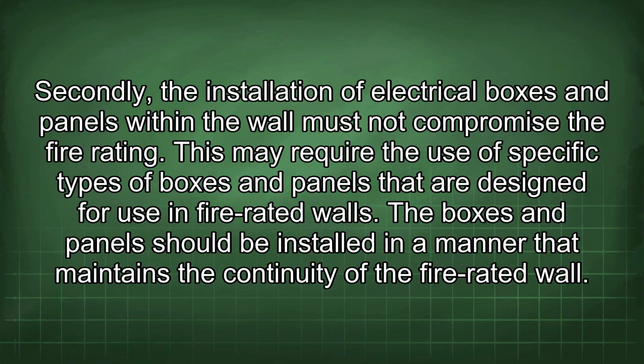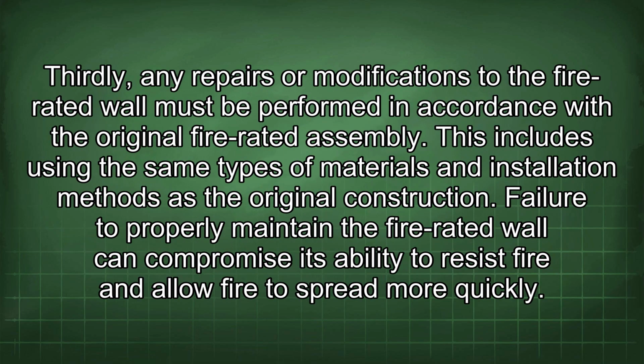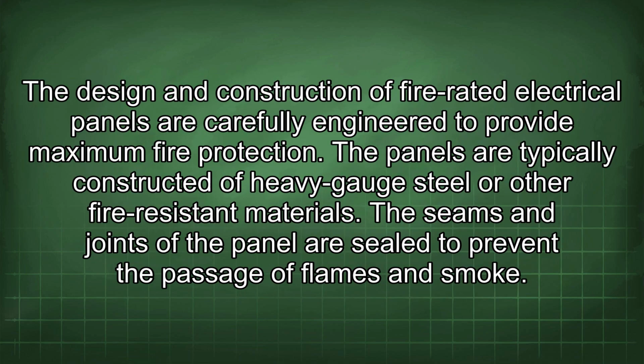The boxes and panels should be installed in a manner that maintains the continuity of the fire-rated wall. Thirdly, any repairs or modifications to the fire-rated wall must be performed in accordance with the original fire-rated assembly. This includes using the same types of materials and installation methods as the original construction. Failure to properly maintain the fire-rated wall can compromise its ability to resist fire and allow fire to spread more quickly. The design and construction of fire-rated electrical panels are carefully engineered to provide maximum fire protection.